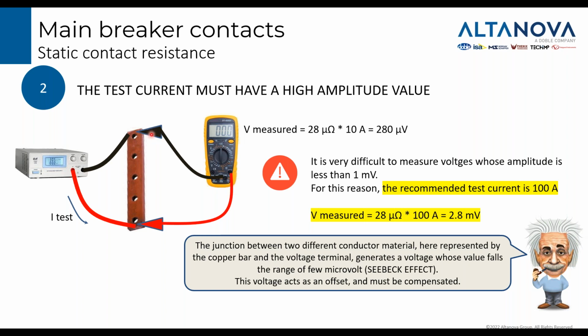At the moment that you connect 2 different metals together, the junction of these 2 metals will produce a very small voltage in the range of a few microvolts. For example, this is the principle that makes a thermocouple work. So you have to take into consideration that a small voltage is created only because you are touching the copper with your clamp, and you have to compensate this value. And believe me, it's very difficult to estimate what is the value to be compensated. So it is highly recommended to find a good high current DC generator.